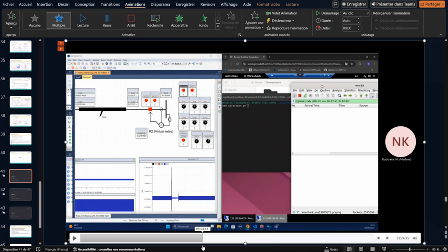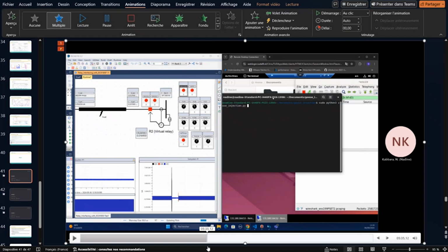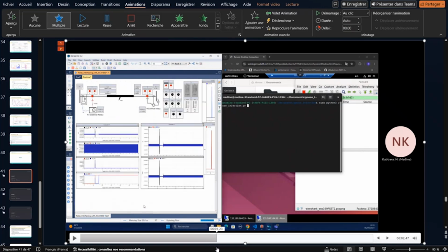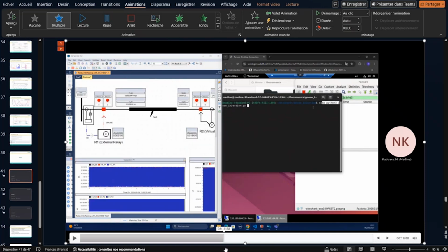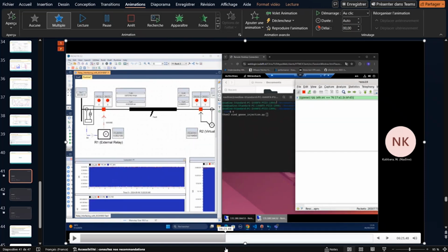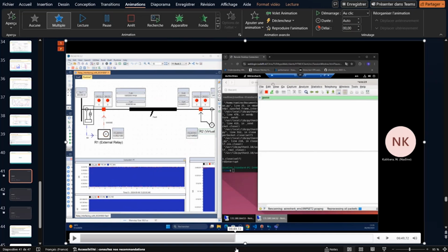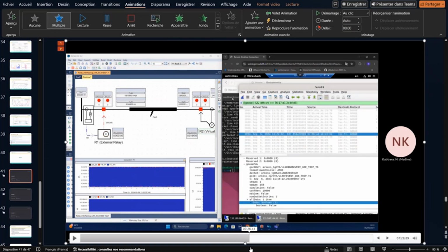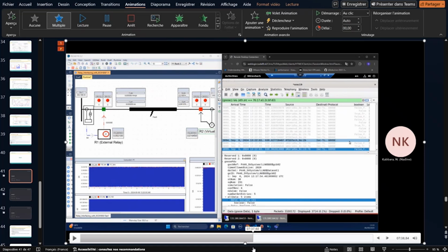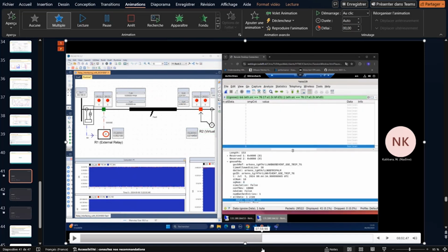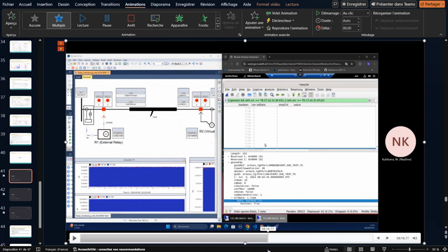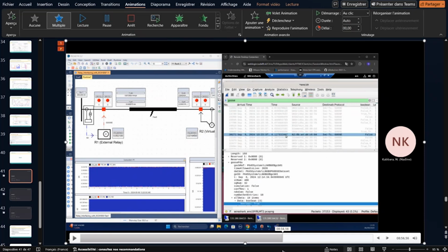So from another VM, we replay a stored packet that we had already collected with value trip equal true, either a GOOSE from the VIED or from the physical IED. And we inject it while the RTDS simulation is running. You can see here that once it's injected, it should turn green. Yeah, here you see it's green, which means that we forced the opening of the circuit breaker, from both a GOOSE configured for the data set from the virtual IED and a GOOSE from the physical IED. It depends where you access the GOOSE.